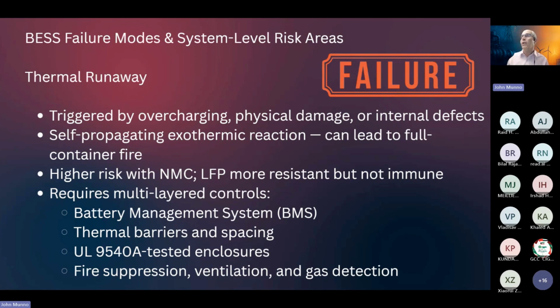So there are trade-offs, but all of them require multi-layered controls: battery management systems, thermal barriers between the cells or the modules, thermal barriers within the containers, and then the spacing. UL 9540A tested enclosures, fire suppression, ventilation, and gas detection.